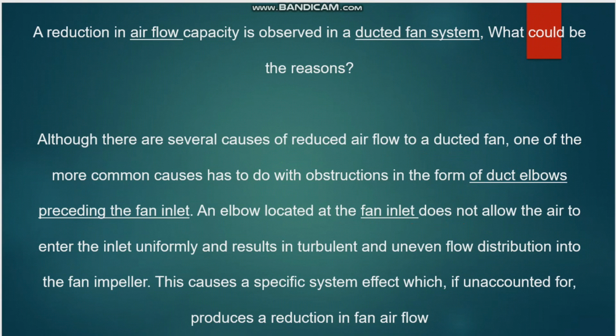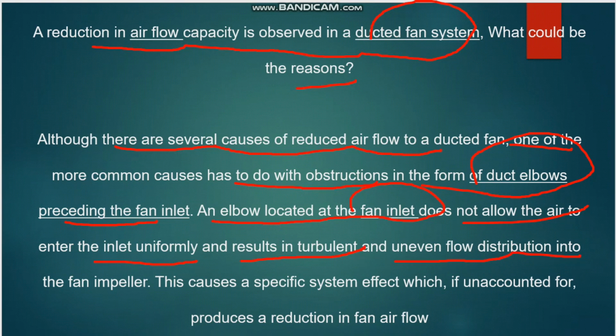And the next question is, a reduction in airflow capacity is observed in the ducted fan system. So what could be the reasons? Although there are several causes of reduced airflow, such as ESP, external static pressure, and other things, one of the more common causes has to do with an obstruction in the form of a duct elbow preceding the fan inlet. That means an elbow located at the fan inlet doesn't allow the air to enter the inlet uniformly, and results in turbulent and uneven flow distribution into the fan impeller. This causes the so-called system effect, which, if unaccounted for, produces a reduction in the airflow.